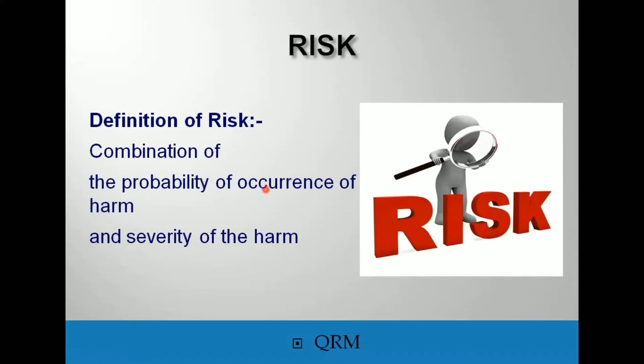First of all, we will discuss the definition of risk. Risk is a combination of the probability of occurrence of harm and the severity of that harm. So as per ICH Q9, what is quality risk management? Quality risk management is a systematic process for the assessment, control, communication, and review of risk to the quality of the medicinal product across the product life cycle. It can be applied both proactively and retrospectively.